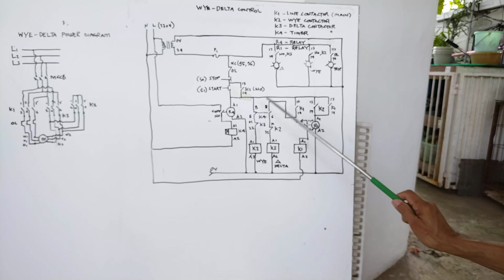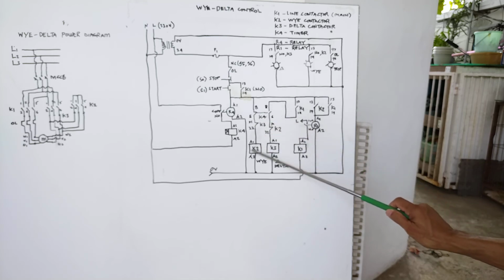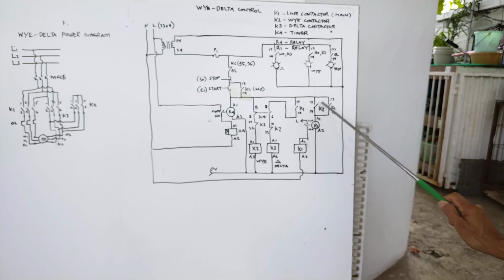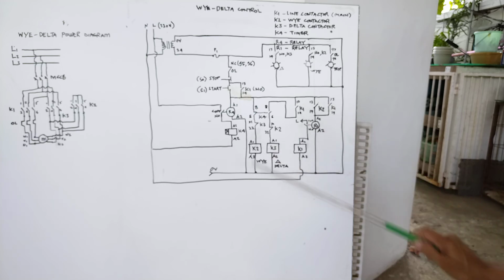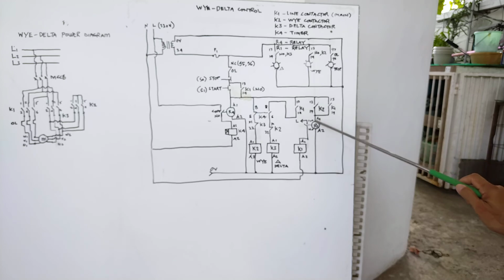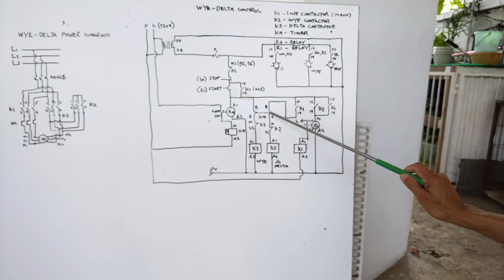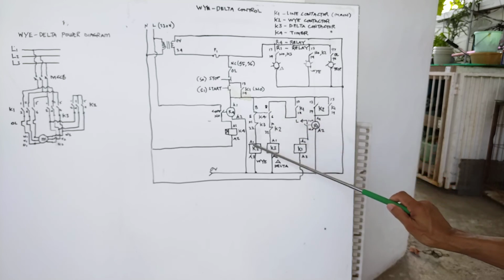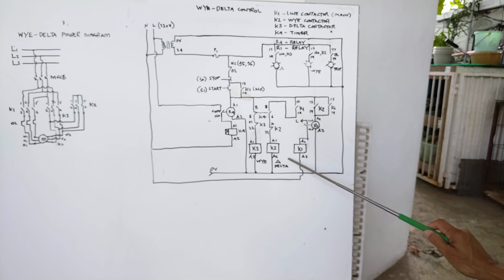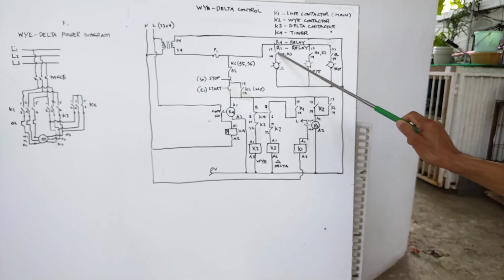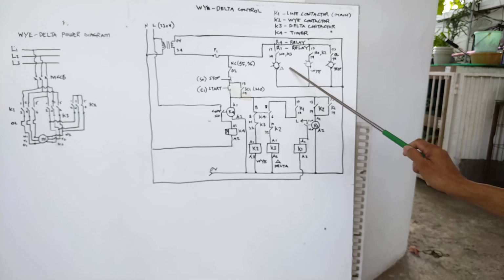After the time delay, which is set there at around 5 seconds, this one will open, de-energizing this and opening this, but the 24 volts can still energize this because this one is already closed when the Y delta contactor is energized. So 24 volts will come here, so it will keep the line contactor energized. Now this one is closed, so 24 volts will come here. Then this one is already closed, and this one is closed because this is energized, then energizing our delta. When delta is energized, this one will close, so this lamp will light up.